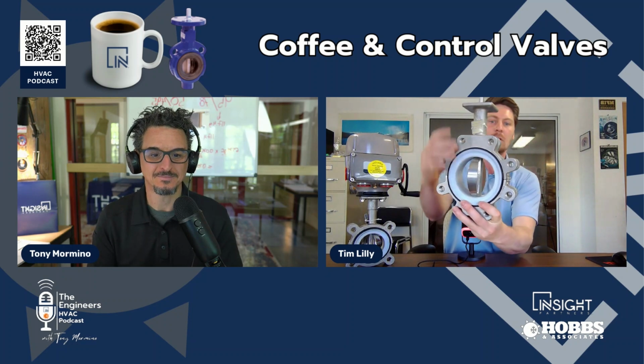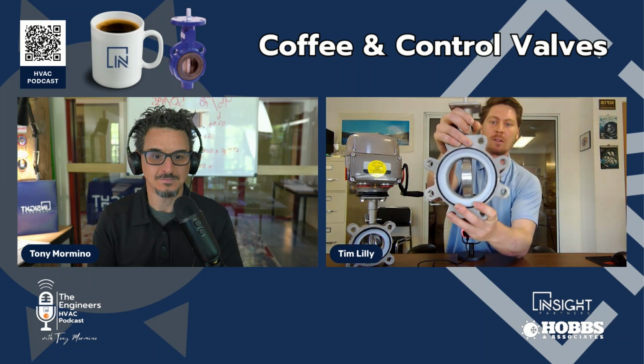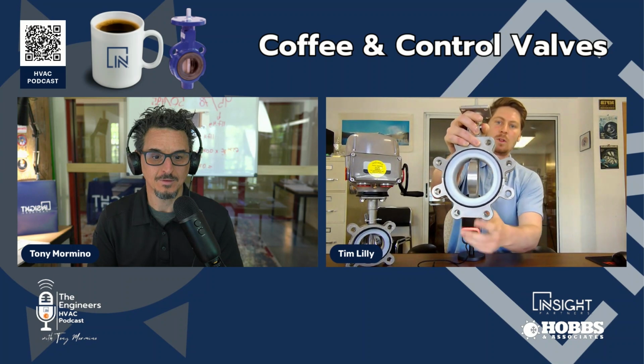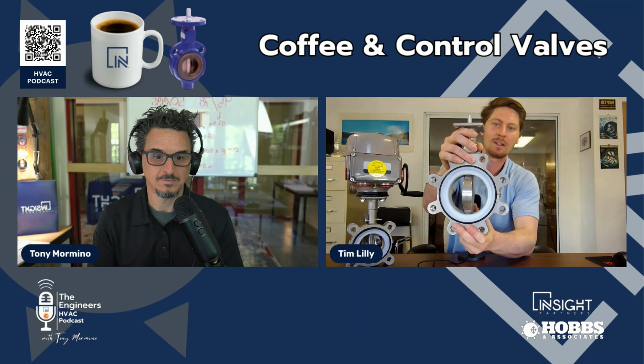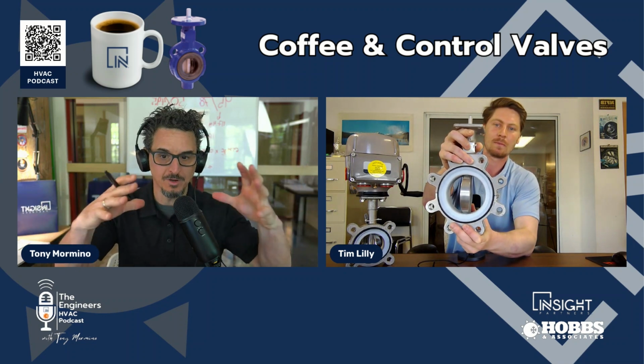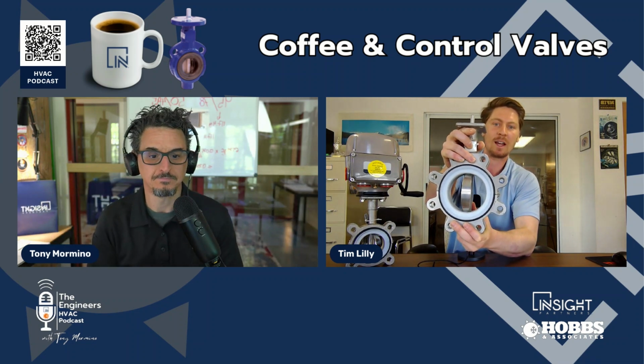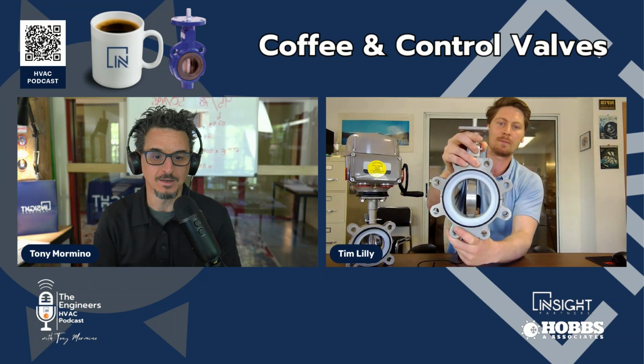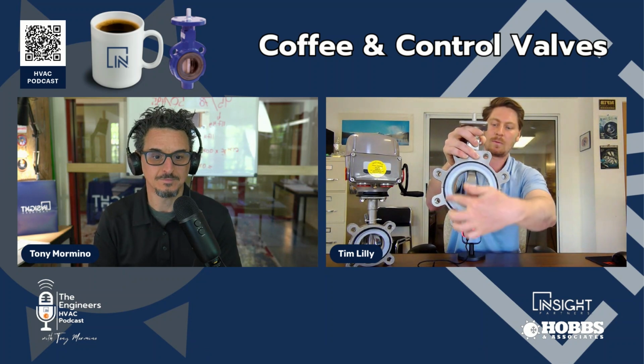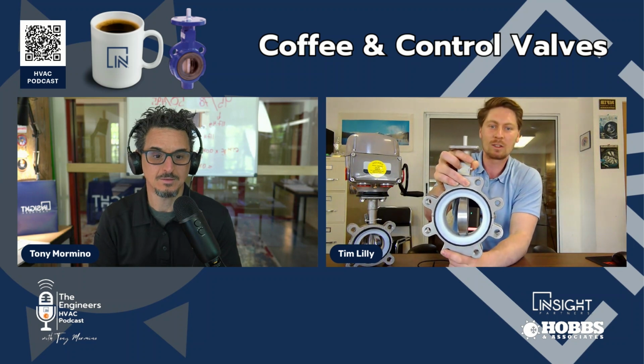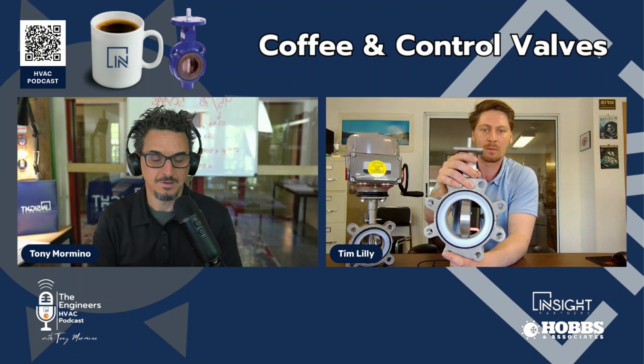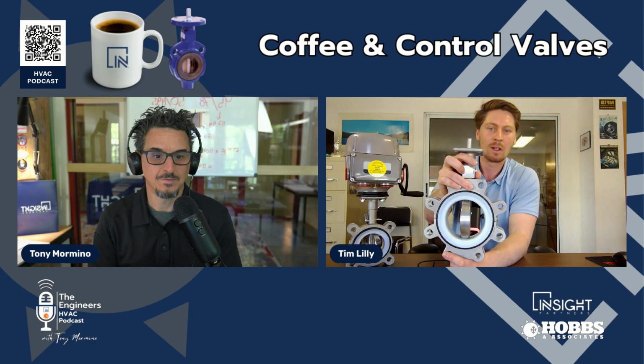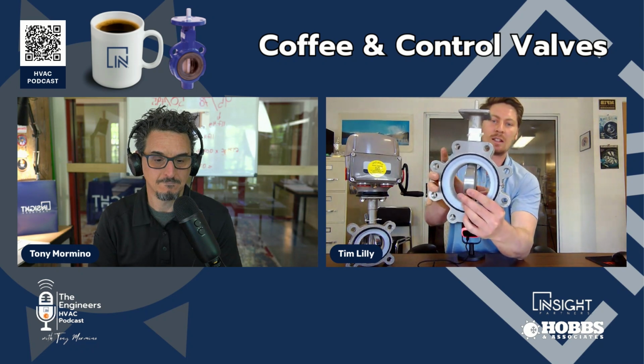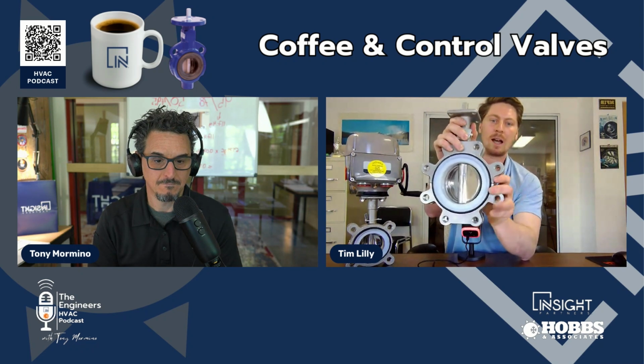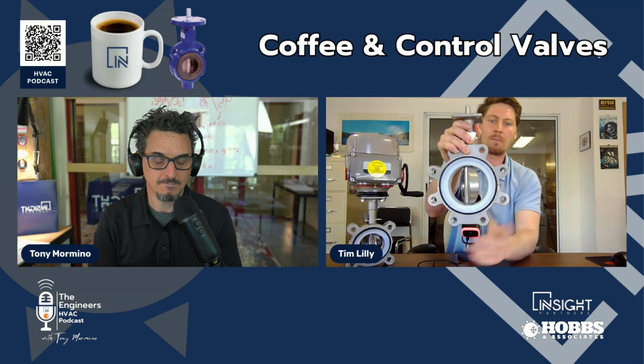Perfect. Okay. So this is a standard lugged style valve, which this is a lug. You can get it in a wafer, but that's kind of a European thing, and we don't use wafers really. Lugs would be where the flanges of the pipe would come to, and you'd put a bolt through there. Those are then called lugs in the valve world. Then this is your resilient seated liner. In your industry, they're all EPDM, which is just a rubber, and it basically makes it a soft seat, an O-ring seat. And then you have your disc, which in a standard butterfly valve, it just goes on off. But with ours, we can modulate.